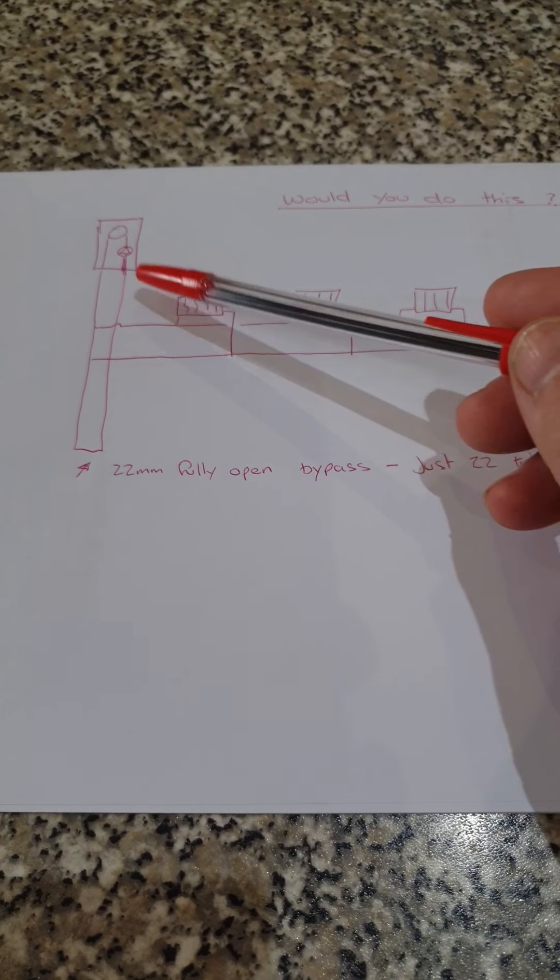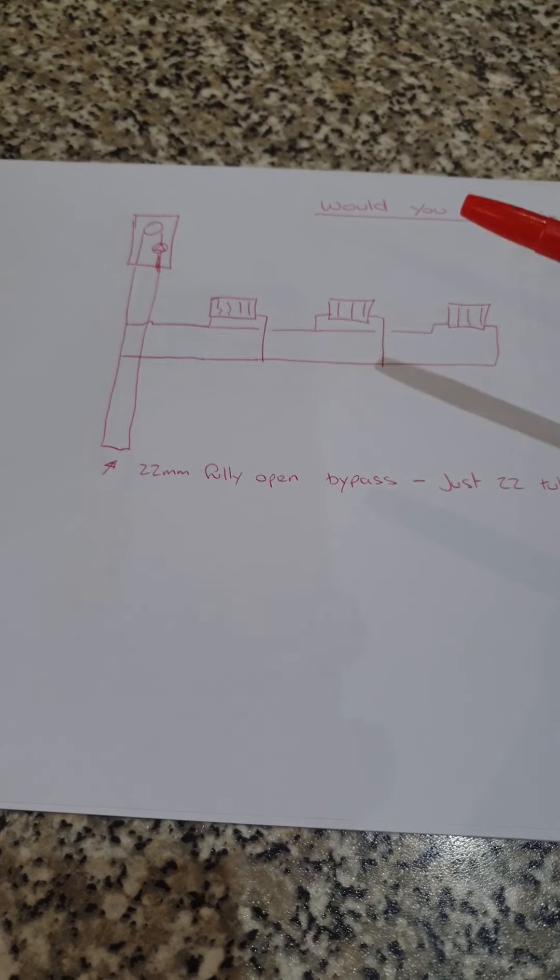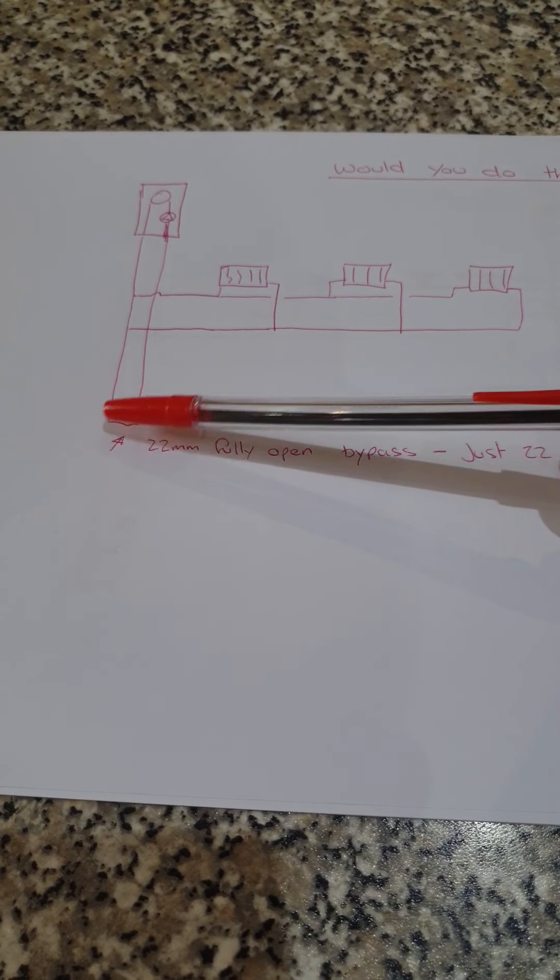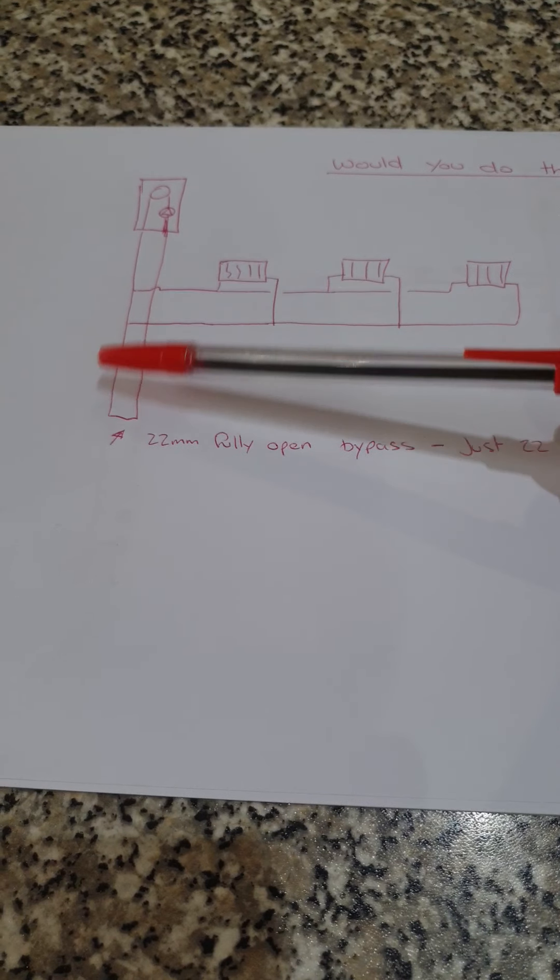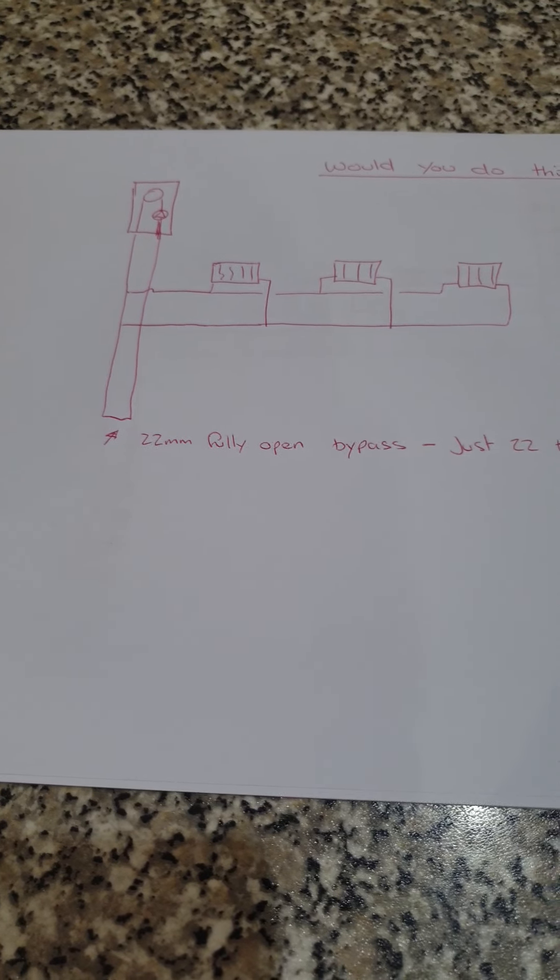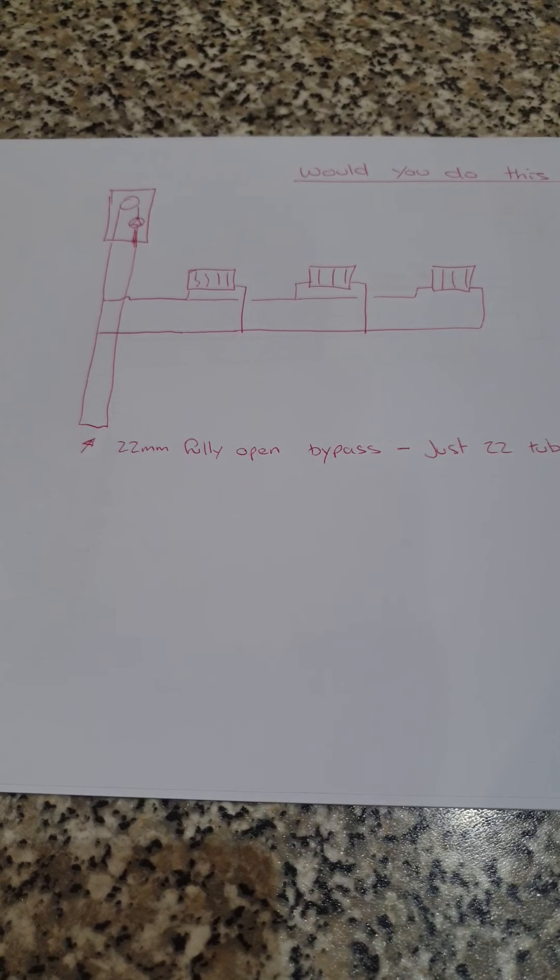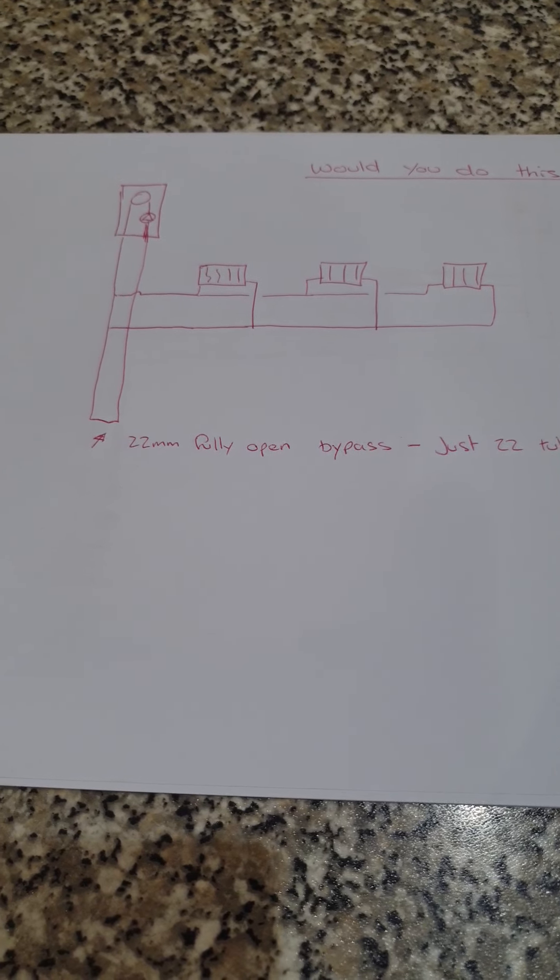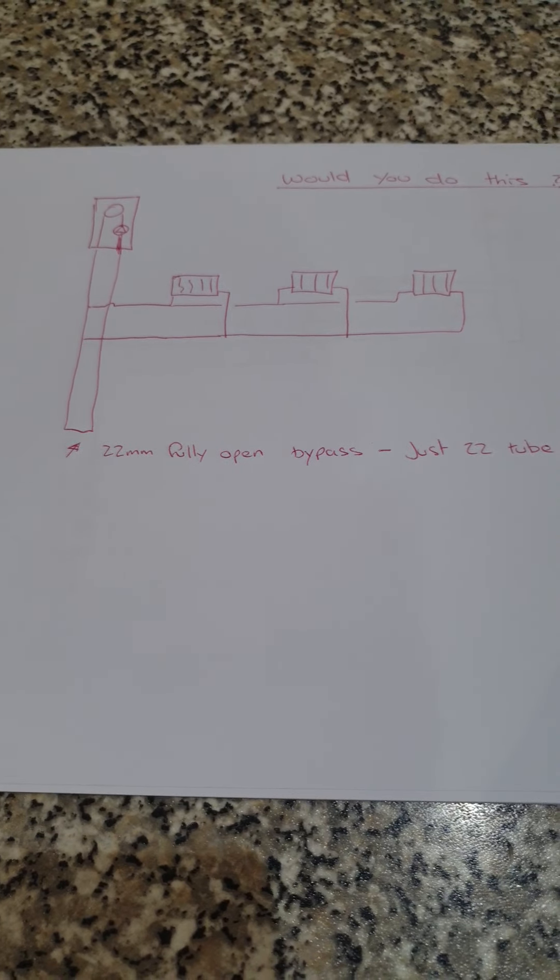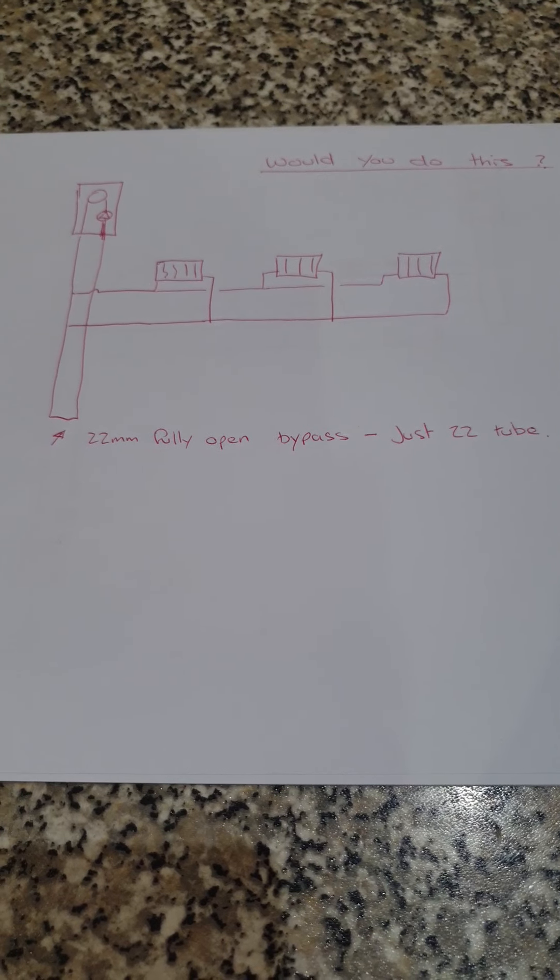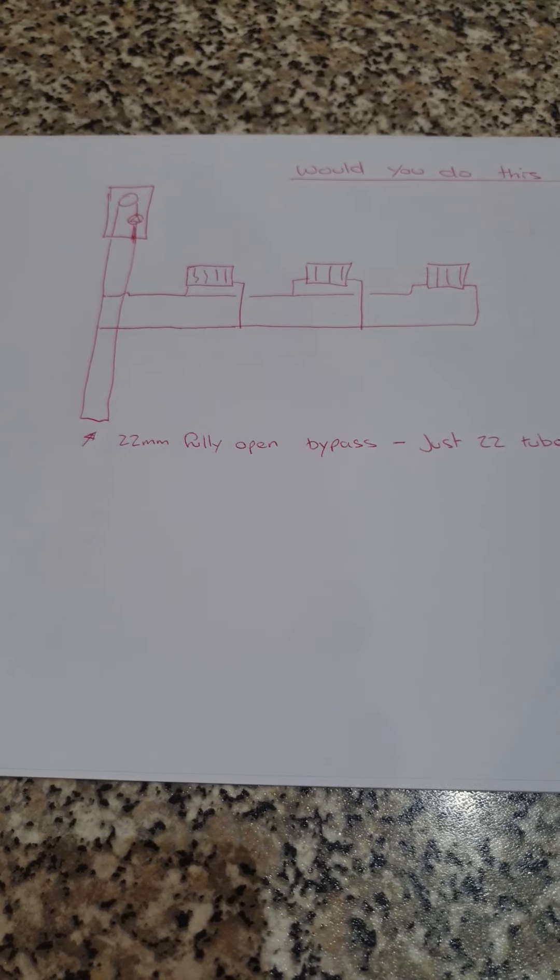We have system boilers, it doesn't matter if a system boiler or not, it's irrelevant. Basically putting in a full bore 22mm bypass in the system with the radiators off the same circuit. Now this to me is just a complete no-no and yet it's what people are doing.